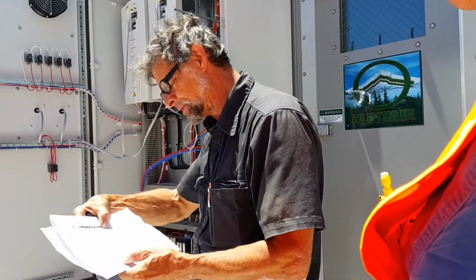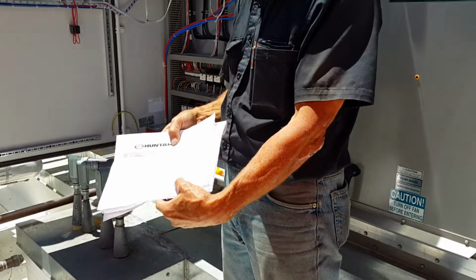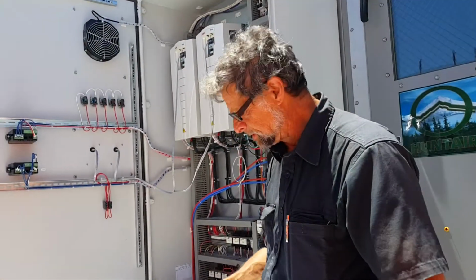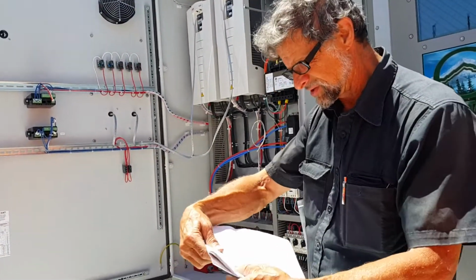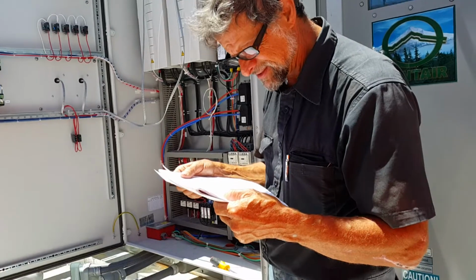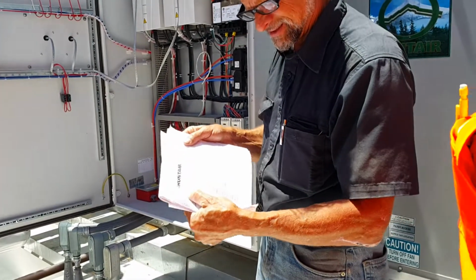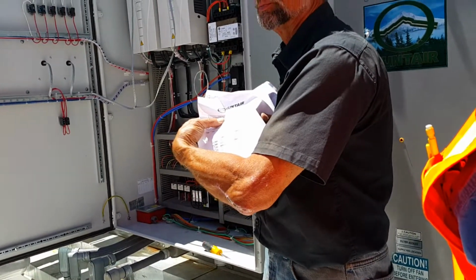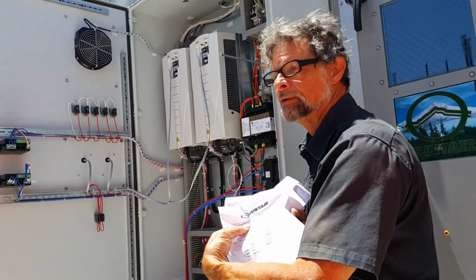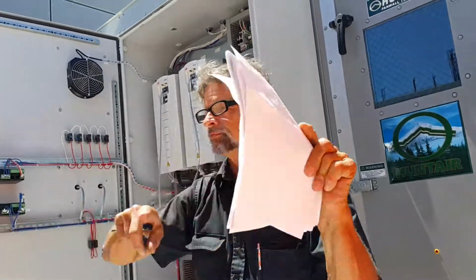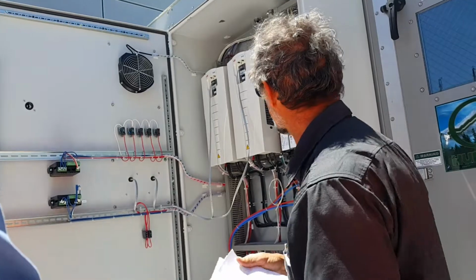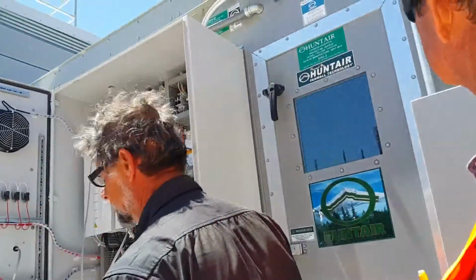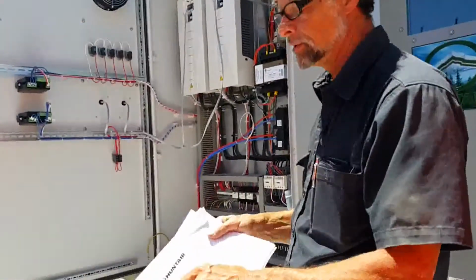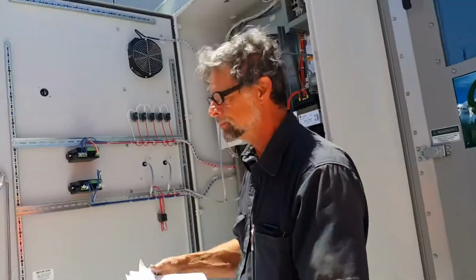Maximum CFM is 26,650. But before I trusted these numbers, I would always look at this up here that says this figure sheet is for AHU3, because during construction you have to shift it all over. So we're actually on AHU3, that's the right sheet. This is how that thing is programmed.